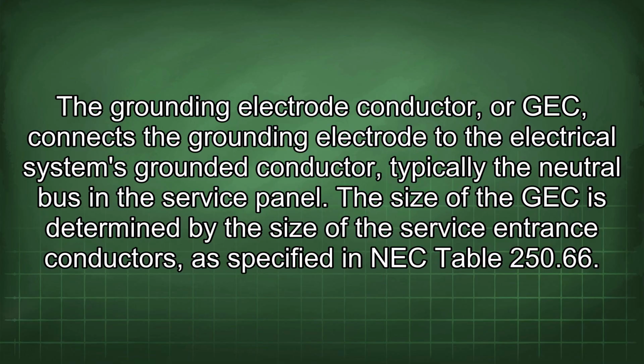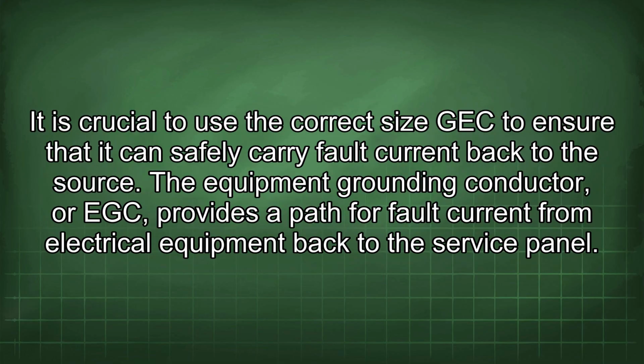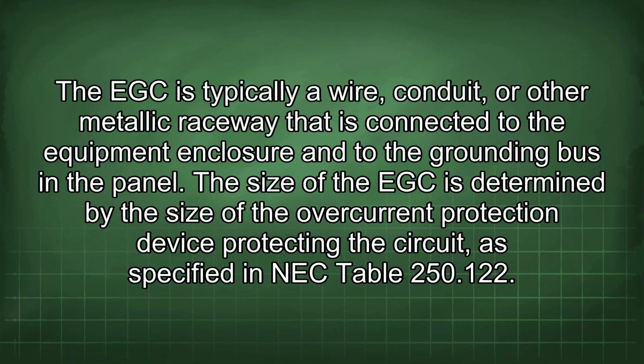The size of the GEC is determined by the size of the service entrance conductors, as specified in NEC Table 250.66. It is crucial to use the correct size GEC to ensure that it can safely carry fault current back to the source. The equipment grounding conductor, or EGC, provides a path for fault current from electrical equipment back to the service panel. The EGC is typically a wire, conduit, or other metallic raceway that is connected to the equipment enclosure and to the grounding bus in a panel.